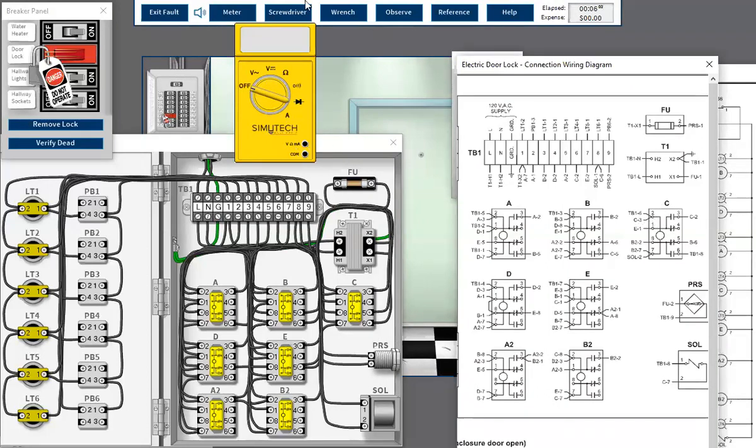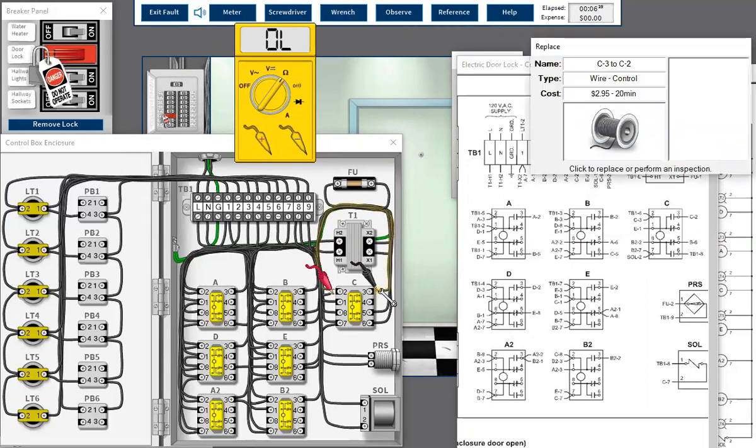All right, so let's get our screwdriver. We're gonna open those up, and I'm gonna check resistance from this wire to this bottom wire here. All right, so from here to here is the connection. This is coming right around there. So what have I got? Oh, well, that tells me that's an open wire right there. So I'm going to go ahead and replace it, okay?